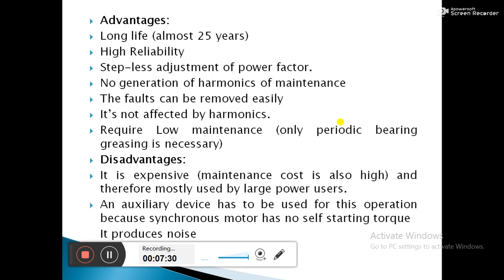The advantages of the synchronous condenser are: long life — its lifespan is about 25 years, compared to the static capacitor; stepless adjustment of power factor; no generation of harmonics; faults can be removed easily; and it requires low maintenance with only periodic bearing greasing necessary. The main disadvantage is that it is expensive, and therefore mostly used for large power users. Also, an auxiliary device must be used for starting since the synchronous motor has no self-starting torque, and it produces noise.